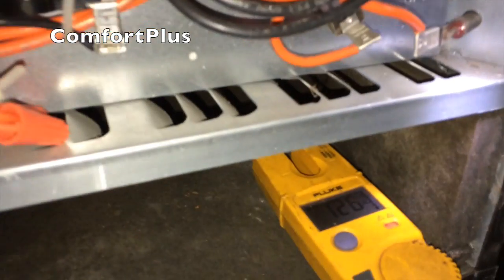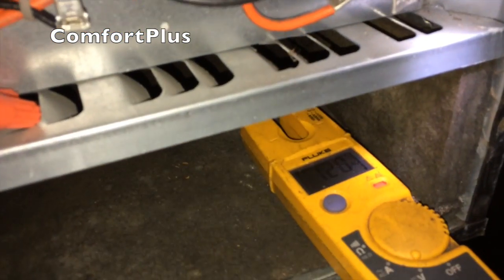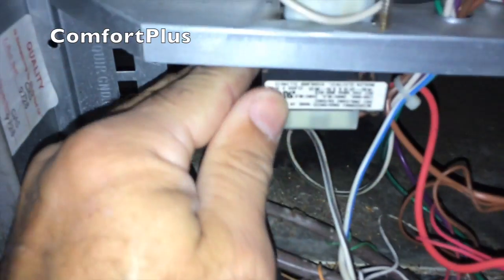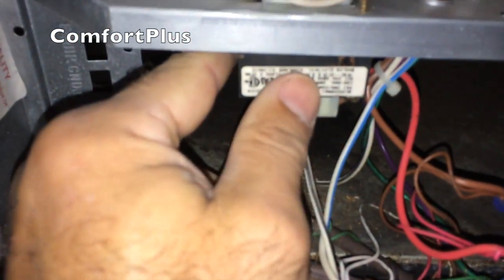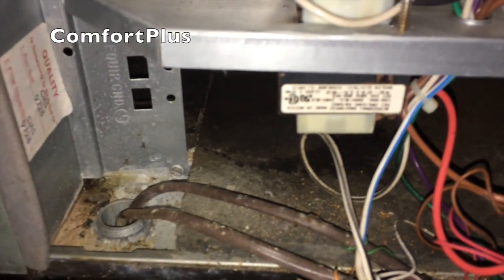Okay, we've got 126 volts on that side, 126 volts on the other side, just for kicks, 253 volts total. The next thing to check will be the transformer to see if there's 24 volts. I don't expect to have 24 volts because the transformer is not humming and it is cool to the touch. So I'm thinking we have a bad transformer.